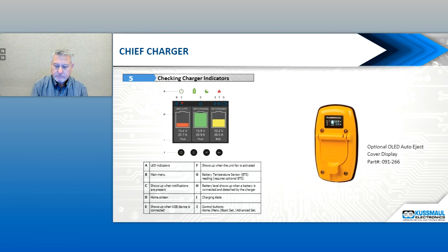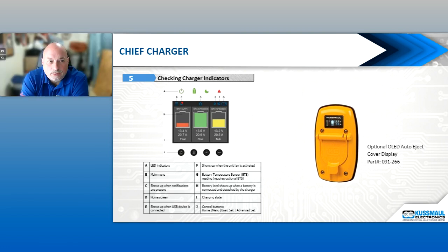One other quick thing, where we talked about the old generation chargers - you had to have a certain voltage of the battery so the charger would see the battery and actually start. The new Chief charger has dead battery charging, so when you plug your auto eject in on the shoreline of the truck, this charger will automatically test the batteries and take off charging, no matter what the state of charge is on the batteries. Now, that doesn't mean your batteries are good, that just means it's going to charge. If your batteries don't come up, then you've got to start testing your batteries and make sure your batteries are good that's in the truck if they're not coming up to charge.